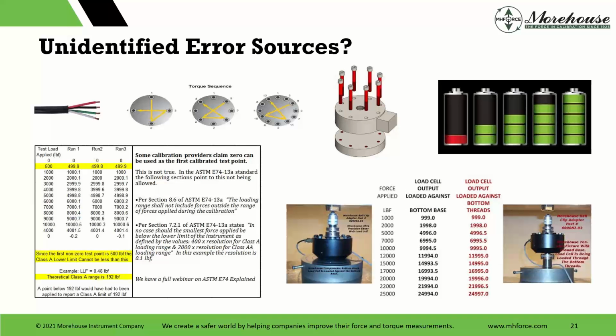Another common error source is not bolting properly. If you're going to bolt a load cell in place, a practice I do not recommend, but some people do, they take it out of a machine and send it to us to calibrate. So we're going to follow the manufacturer's specs, and we're going to use a star pattern.